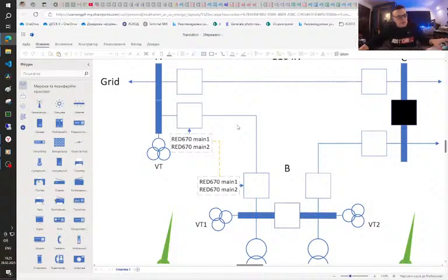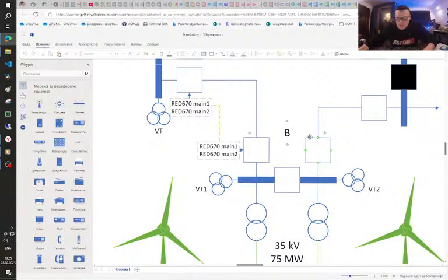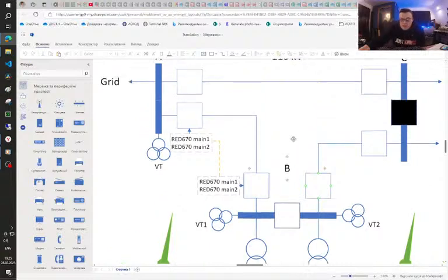Okay, and usually the pause in AR cycle is about 2 to 4 seconds. In this case, on substation A, the AR pause was about 2 seconds, and on substation B, AR was about 2.5 seconds.